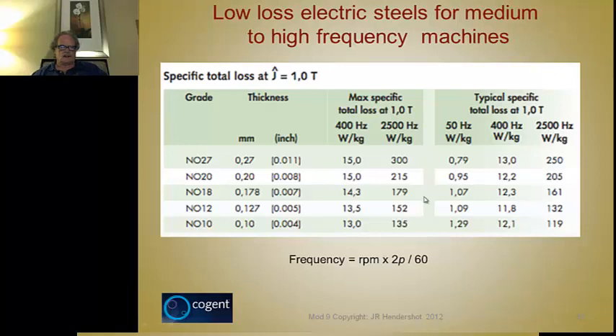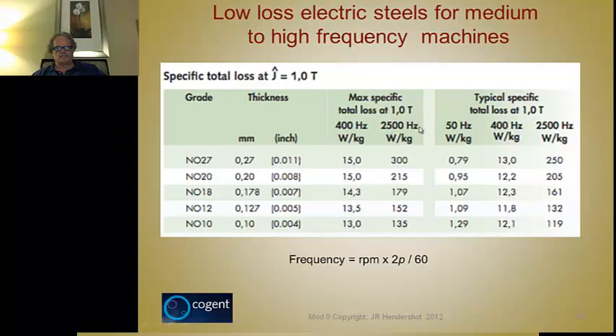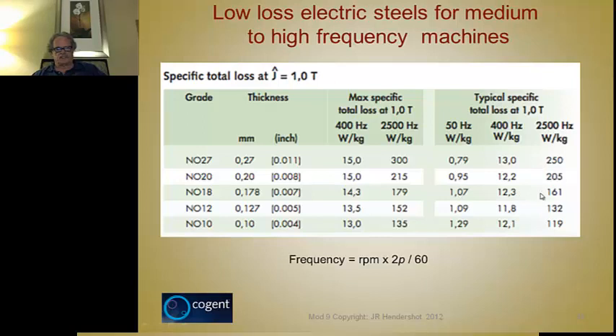For medium to high frequency machines, here's newer data on very thin steels for high frequency applications. The flux density is still limited to one tesla, but at least they give loss data in watts per kilogram at 400 Hz and 2500 Hz. The comparison of 50, 400, and 2500 Hz shows how drastically core loss increases as a function of frequency — it's really significant. The frequency here is the electrical frequency: pole pairs divided by 60, times the RPM.